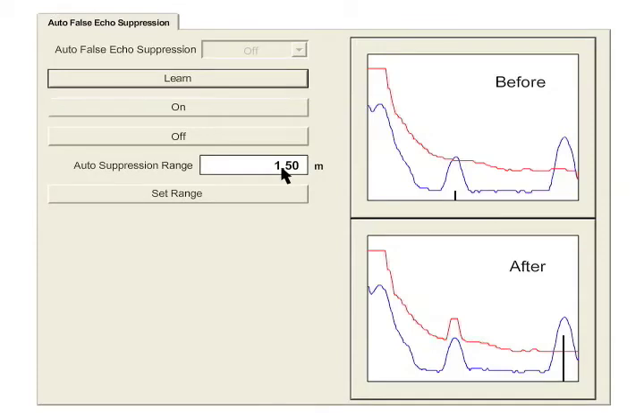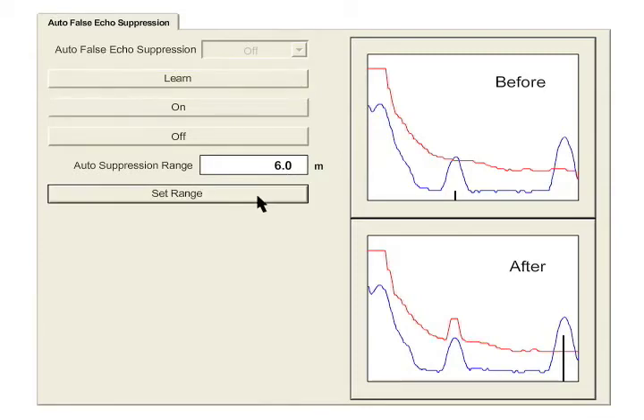In our example, the material echo is at 6.5 m, so we will enter 6 m into the range field. We then click on the Set Range button and then the Learn button to turn on Auto-False Echo Suppression.